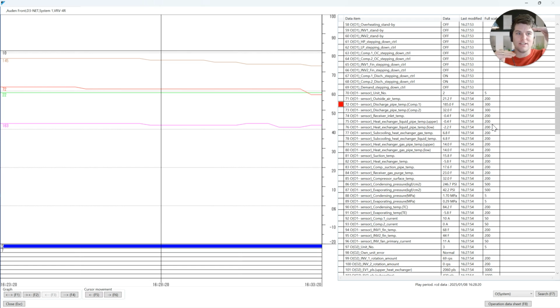There's no other reason why my refrigerant would pick up a huge amount of heat if it's the right volume, right? If it's the right volume and temp coming in, it should be the right volume and temp coming out. If it's not, that additional friction we're picking up is scroll plates on bearings rubbing together without any kind of lubrication. It's metal on metal action, which creates excessive friction, which we now know goes into the refrigerant, which we can measure. All right, so that's discharge superheat and why it matters.